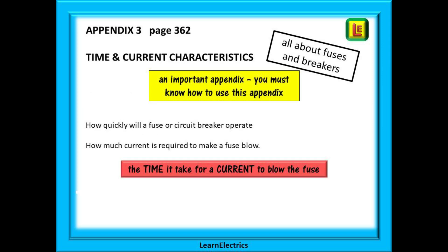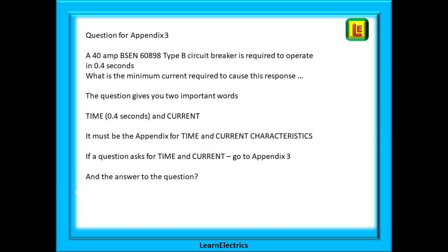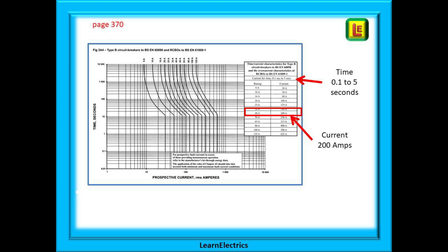Appendix 3 is all about breakers and fuses. The title includes the words time and current characteristics, so if a question comes up about a fuse or breaker and mentions a time and a current then this is the place to go. A typical exam question might say: a 40 amp BSEN 60898 type B circuit breaker is required to operate in 0.4 seconds — what is the minimum current required to cause this response? The question gives you two important words: a time (0.4 seconds) and current. It must be the appendix for time and current characteristics. Find page 370 for BSEN 60898 type B breakers and there in the chart on the right is the answer.